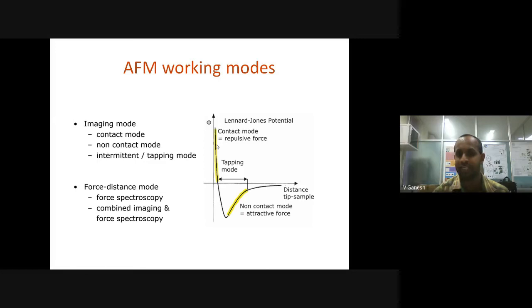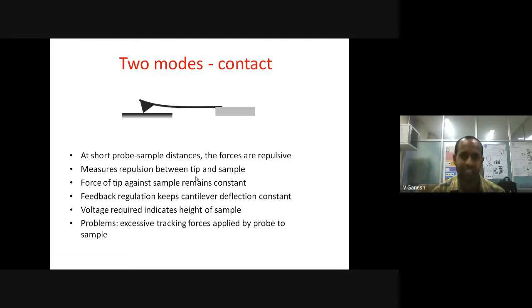Apart from these two modes, we do have a tapping mode, which is a kind of intermittent regime between non-contact and contact mode. These are the modes I highlighted a while ago. One can measure either the repulsion or attraction between the sample and the tip, depending upon the nature of the sample and the surface arrangement.